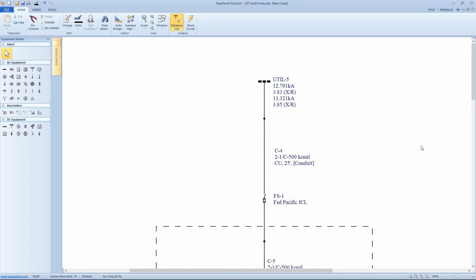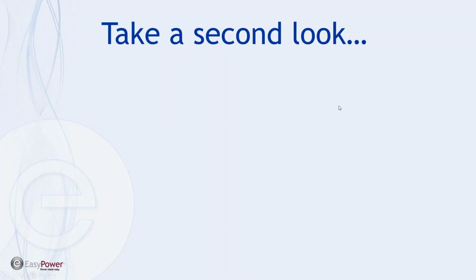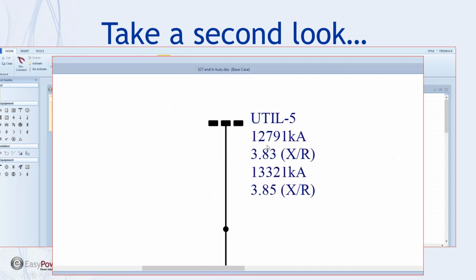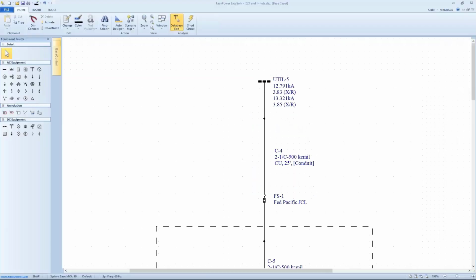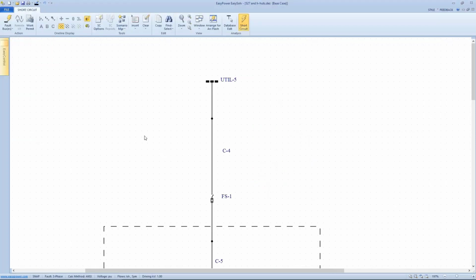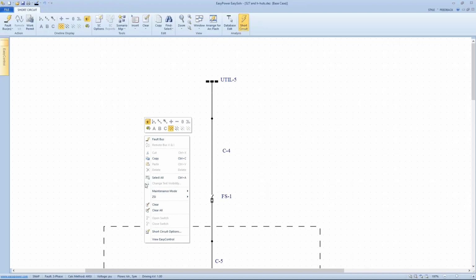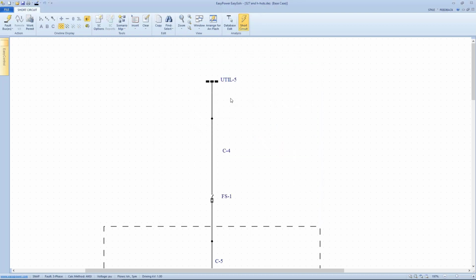Okay, so again, what we want to do is make sure we enter the data correctly, and especially in the early stages, use a bit of a jaundiced eye looking at the units involved when we're doing data entry. All voltages in EasyPower are in kilovolts, and you'll see you can actually adjust this. Let me go back to the tool. As we get into short circuit, if you right click in an open area and go to short circuit options, my units are going to be in kiloamps no matter what I do. So just be careful that you're entering the data appropriately.